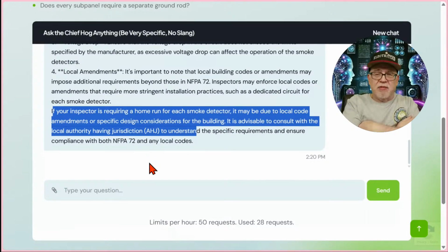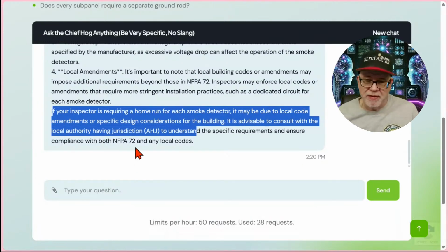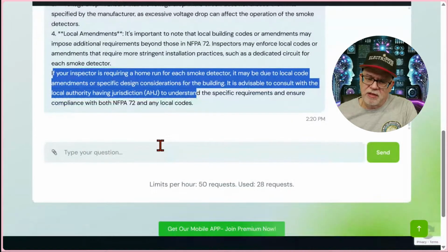Because they don't give you that many lugs, that many termination points, in a fire alarm control panel. I have seen some buildings that are massive, with so many smoke detectors that I just don't see how it would be plausible. So a small system, maybe. But I don't think there's anything in there that would require that, so I would have pushed back. But anyway, the good news is that it does cover those type of things.